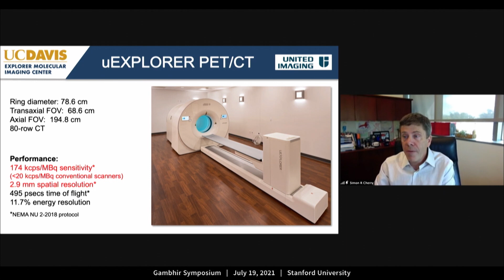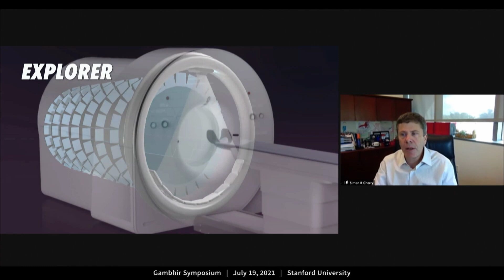So here's a very short video to show how it's built up from a single individual scintillation crystal into arrays of crystals that are read out by 4 silicon photomultipliers. That's how the light is converted into an electronic signal. That's built into a panel. There are then 24 of those panels to build a single ring unit. We then replicate that another 7 times to create a scanner that has an axial field of view of almost 2 meters. And as I mentioned, it's over 500,000 individual detectors. This rivals the complexity of some of the high energy physics experiments at CERN, just to put in perspective how complex our medical imaging technologies have now become.